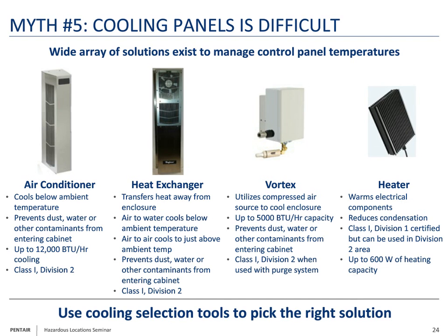So you can use an air conditioner, which cools below ambient temperature. The air conditioner is sealed, so it prevents dust and water contaminants from going into the control panel, and it can provide up to 12,000 BTU an hour of cooling capacity, and they're Class 1 Division 2 certified, so they suit a larger control panel like a distributed control system or a PLC cabinet, for example. Heat exchangers really transfer heat away from the enclosure. Air to water would cool below ambient temperature. Air to air cools just above ambient temperature.